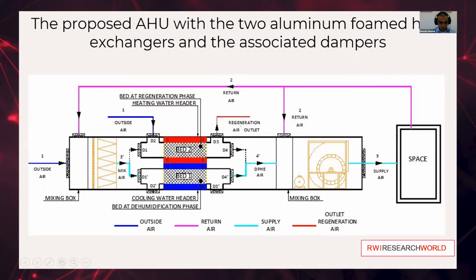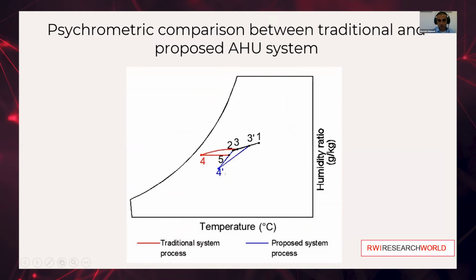A COMSOL numerical model was set up to investigate the performance of the two beds in order to know the conditions of air after the bed. It can be noticed that the levels of heating and cooling temperatures for the thermal fluid can be provided by low energy sources, unlike the traditional system. In the psychrometric chart process, the red lines refer to the traditional system process, while the blue lines refer to the proposed system process.